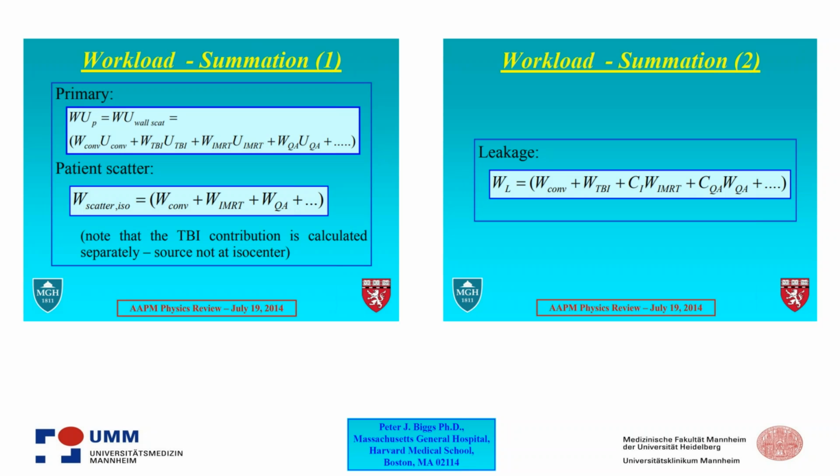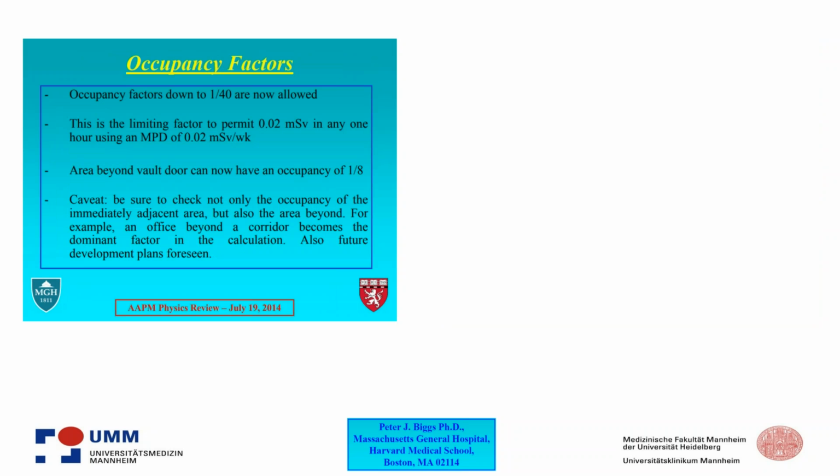At the end, you will not get a license to operate the machine until the radiation protection for this situation is correct. So if you have a bad radiation protection plan, this will prolong the installation time for the machine, and it will increase the construction costs. So that's very, very important.